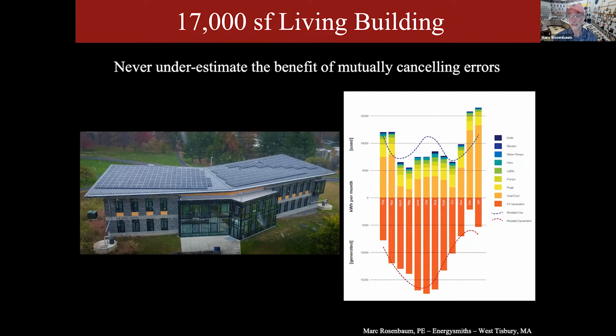On the right, the dotted lines are my model and the bars are the actual data. You can see that I underestimated the heating load, and I'm not sure exactly where that comes from. It could be the heat pumps working at a lower COP than I guessed in my model. It's challenging to guess the actual COP of a heat recovery air source heat pump system. You can also see that I overestimated the cooling in the summer. So this building ended up within a few percent of what I predicted overall, but where it actually uses energy is different than what I predicted. It takes some good fortune as well as a good model to end up with one that really conforms exactly to what the building is doing.